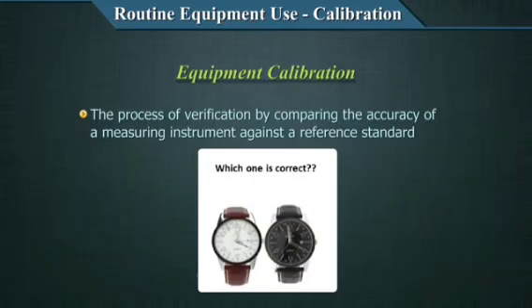Equipments need some kind of a coarse tuning. If you remember, there's a coarse tuning, which is your adjustment of your equipment, and some fine tuning are done for the analytes using some material called calibrators. Both these concepts are important, though in this video we'll only talk about the equipment calibrations. When you're looking at this picture, let's assume that the reference standard is a white dialed watch. So comparing to the white dialed watch, you see that the black dialed watch is about 4 minutes slower.